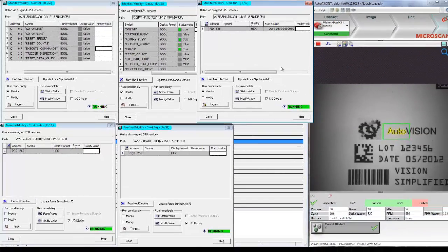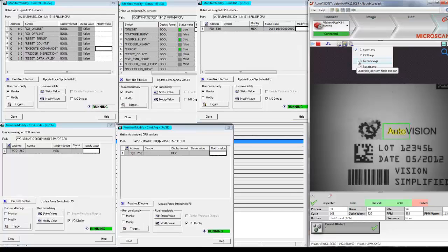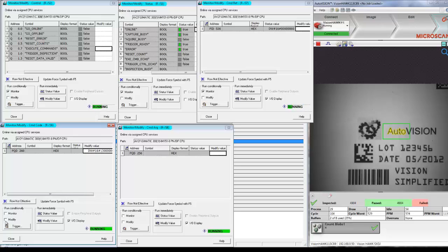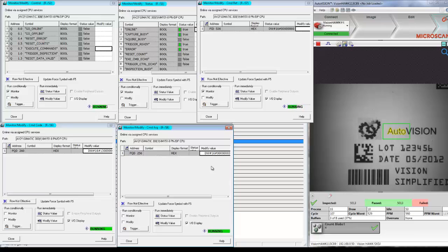There's a command return field, which can be used for querying what job is currently running on the camera. So let's say that I want to change from the current job number one to the decode job number three. The first thing you do is enter the command code. For going offline, switching job, loading the job, and going online again, it's 13 followed by six zeros. We enter that value and make sure the camera gets updated. The next step is to select the job we want to switch to, which is three in our case.